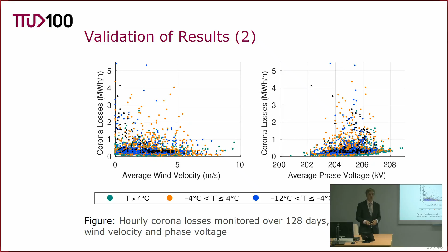In conclusion, I have developed and presented a method to calculate Joule losses and corona losses as separate components using PMU measurements. The results of monitoring corona losses have been validated based on this comparison of the dependence of corona losses on these weather parameters. We can monitor corona losses over longer periods of time and detect events when significant corona losses are present. This is a necessary input to obtain forecast models that enable corona losses to be forecasted and possibly reduce the expenses on loss energy imbalance.